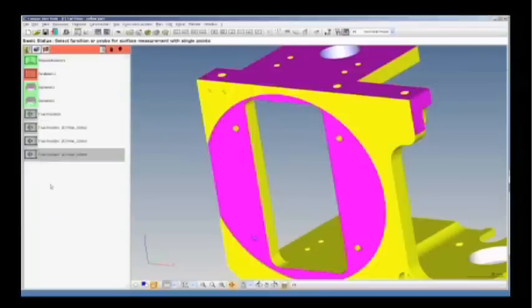Exactly. It's a shortcut. Realistically, this is going to be a much longer part program with lots of objects in there. And actually, even with that, as I build this long measurement plan, a full layout of the part, I may want to start doing some management of that. The front face may be done in an operation. The top part might be done in a second operation. And instead of building different programs, I would have just one complete measurement plan and manage that product.